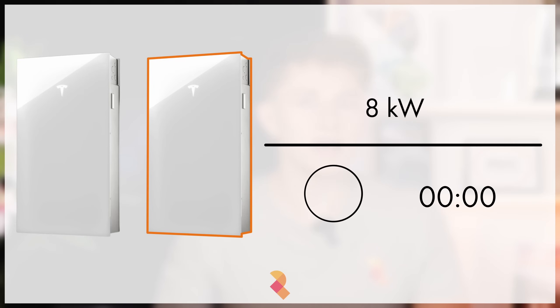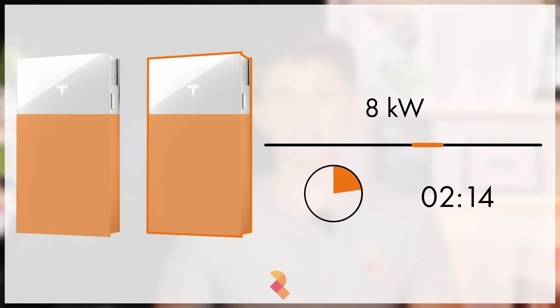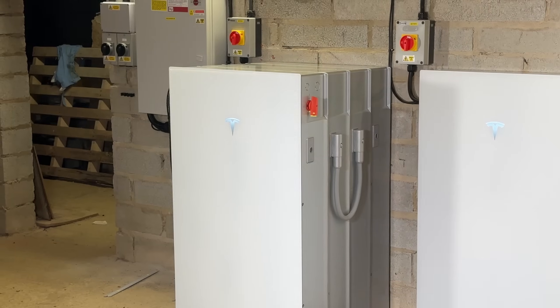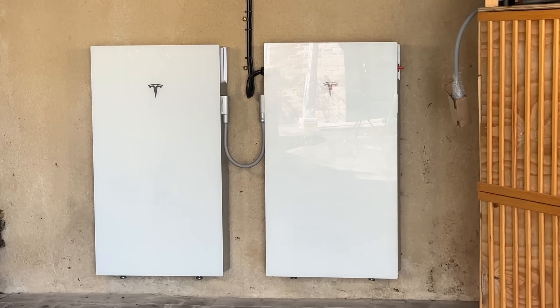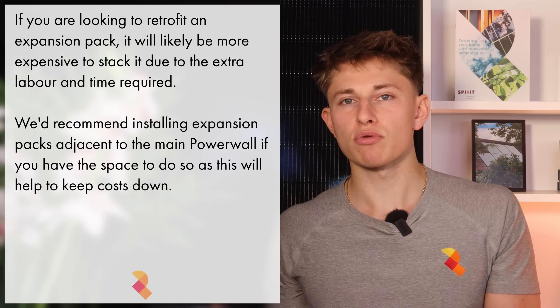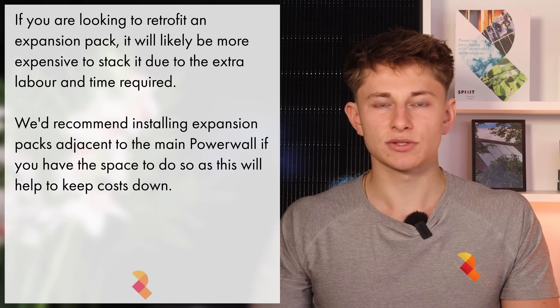If you do install an expansion pack, your charge rate also increases, and the entire system will charge at 8kW instead of 5kW. There are two ways to install the expansion pack: it can either be stacked behind the main Powerwall 3 or mounted adjacent to it. If you're getting an expansion pack retrofitted to an existing Powerwall 3, I'd definitely recommend mounting the expansion adjacent to the main Powerwall 3 if you can, as that will certainly be a cheaper and quicker install.